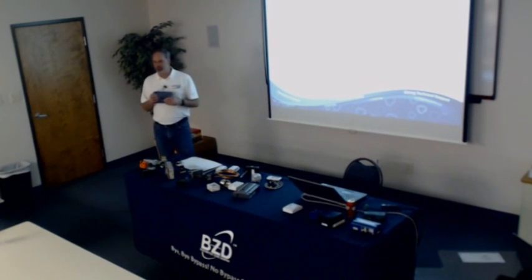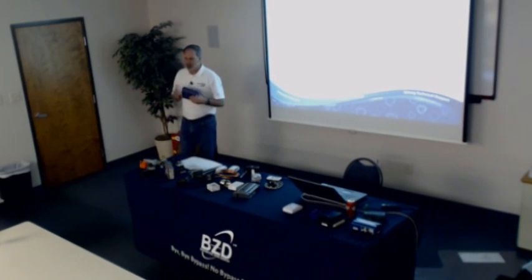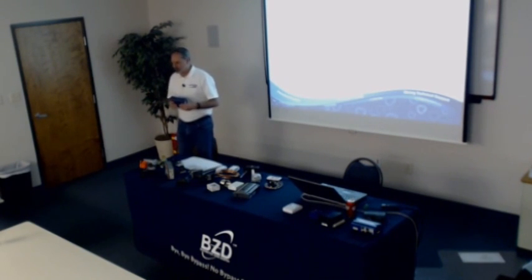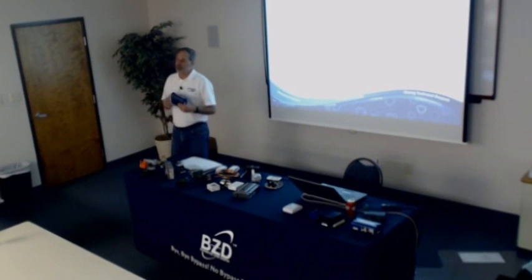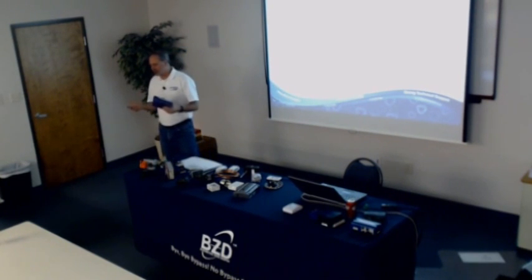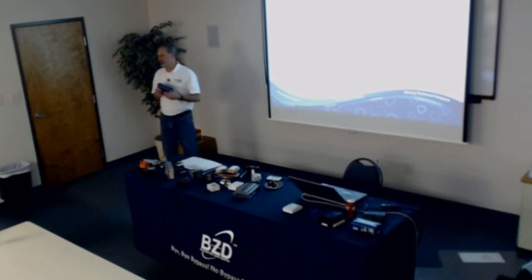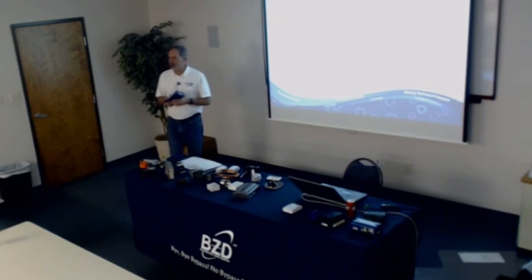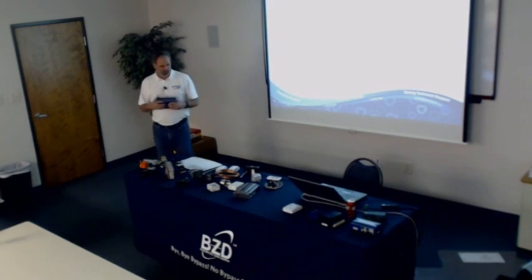At the same time, when we were at the Trane company, they had wireless thermostats on the wall, and once a week, if I was in the office, I would get a phone call from somebody saying, hey, my office is uncomfortable, can you check into it? And we had an office maintenance person, and I said, well, can you have the maintenance guy check the batteries? And they said, well, he's not around. Well, the control system could see the battery strength, so we'd look at it online from my desk, and yeah, your batteries are dead. And we tried to get the maintenance people to change the batteries every January. The batteries were rated for 2 years, and they usually lasted a little over a year. But we said, if you change the batteries every January, it's probably going to be okay. But it's just something else to maintain.